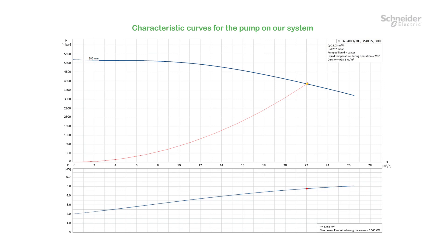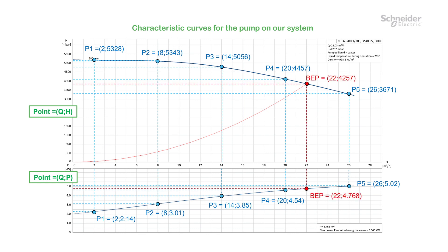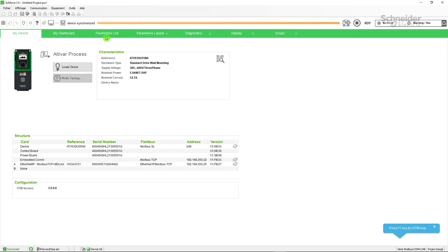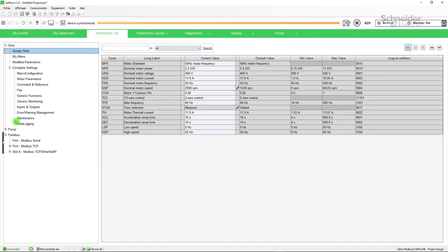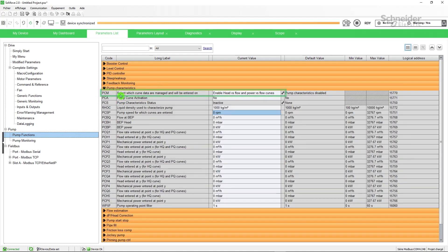On the pump manufacturer curves, choose five points sufficiently spaced and identify their coordinates and those of the BEP: P in kilowatt, Q in cubic meters per hour, and H in millibar. These coordinates will allow us to enter the curves in the drive. Set the points with SoMove. Go to pump characteristics menu on SoMove software.